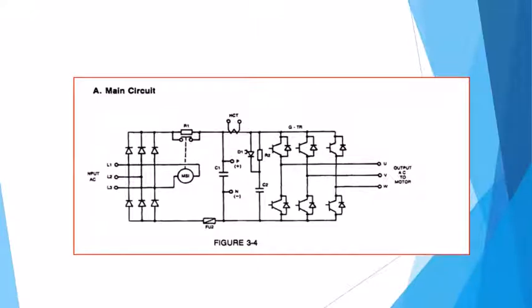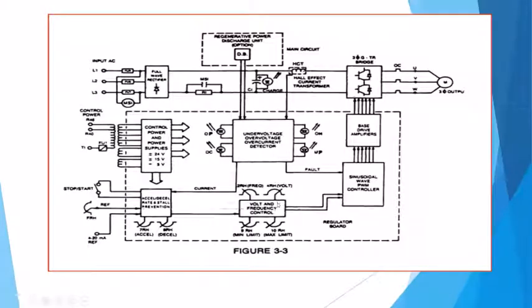VFDs really haven't changed that much since the 80s, other than we have a lot of very fancy digital processors on the front. This happened to be the old original Toshiba diagram that I had back in the 80s, where everything was done by potentiometers. We set our upper voltage, we set our acceleration or deceleration limits. We basically set all of those, and that just went into the processor that drove the transistors. It had the upper voltage and lower voltage, but we had no real microprocessors at that time, so we had to do it all with the old potentiometers, read the voltage: I get this much voltage, it does this. Much harder to set up, and some of the older drives were as big as phone booths.